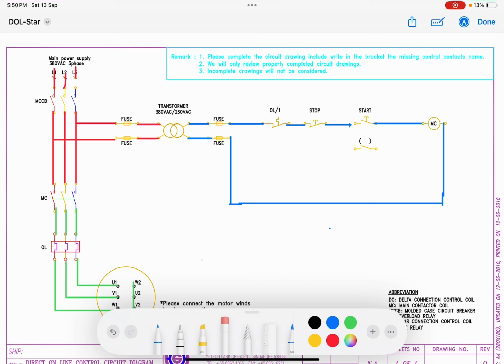So now we can test our circuit. Once I press this start button here, what will happen? This MC will get energized, right? And once it gets energized, it is going to close its main contact here, right? But you also need its holding contact, or the auxiliary contact, and it has got one auxiliary contact here. So the missing symbol that we have here is the NO contact of your magnetic contactor MC. So why is it given? Because as I already told you, this start push button is a spring loaded start push button. So only when we are pressing this one is it going to make this contact, and as soon as we release the start push button, it is going to open up and our motor is going to stop. So this is what is going to take place.